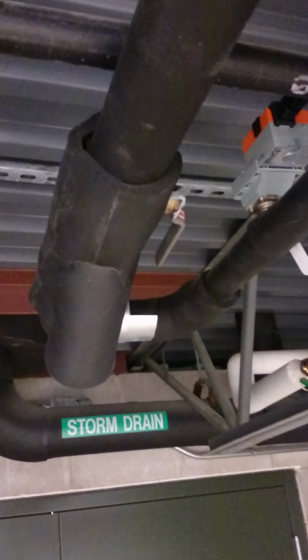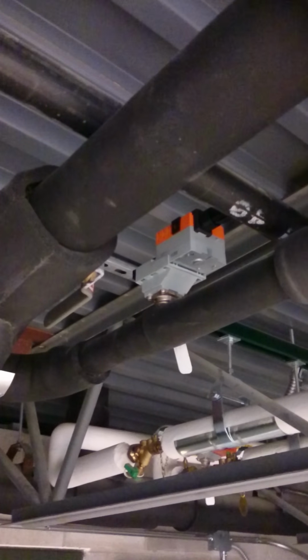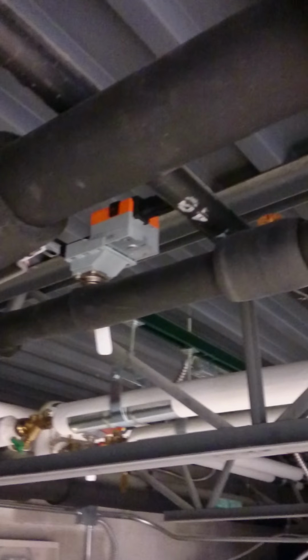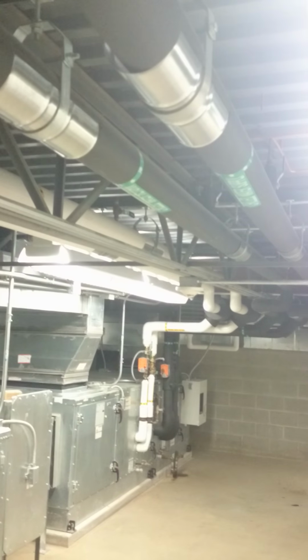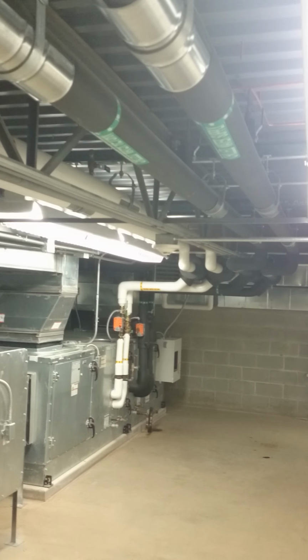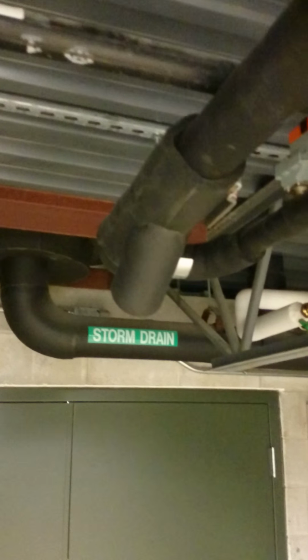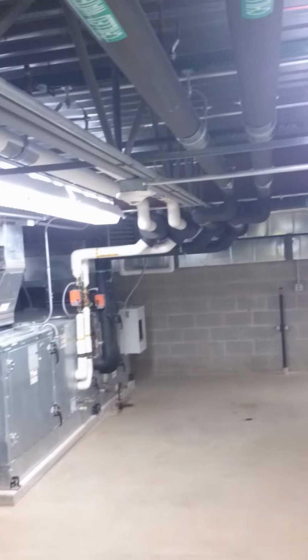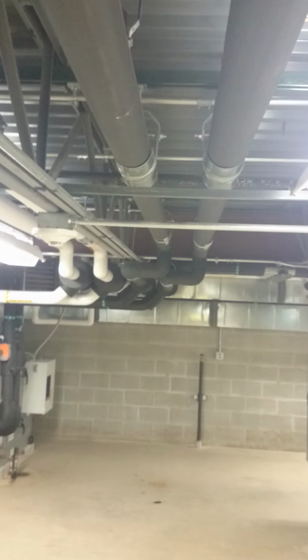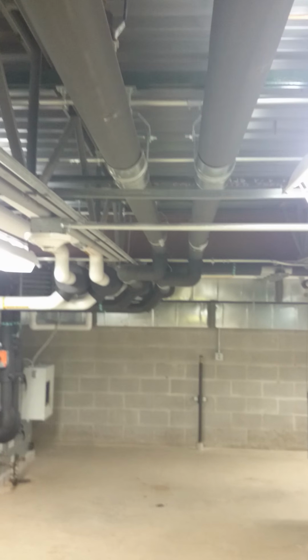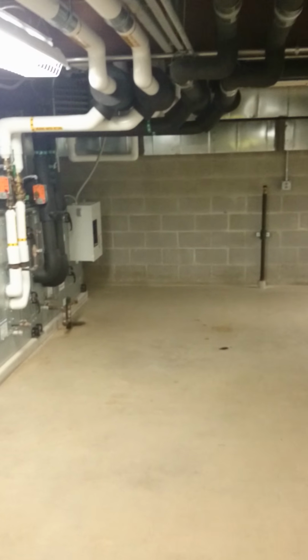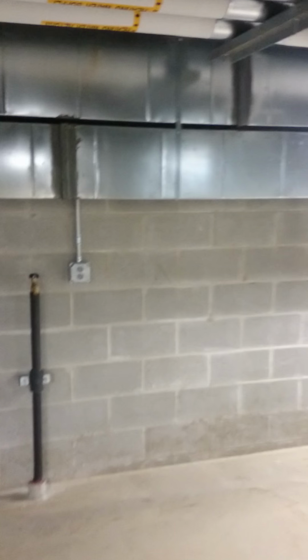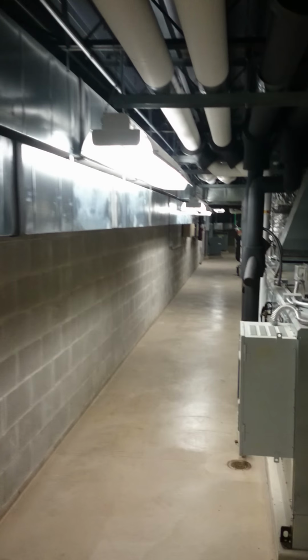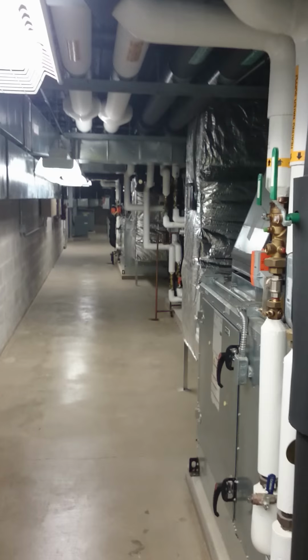And to prove the value of looking through your blueprints, being familiar with piping and ductwork on the blueprints, I did find the original blueprints from when this wing of the school was added, and found that sure enough there was supposed to be a valve there. Of course, it's been too long to really go back on the contractor that installed the piping at that point, but they just wanted to eliminate the problem, so they contracted us to go ahead and install that bypass. And since then, no Freezestat, and then we were able to enable the two compressors with that other resistor, to get all four circuits working. So everything's been working great since.